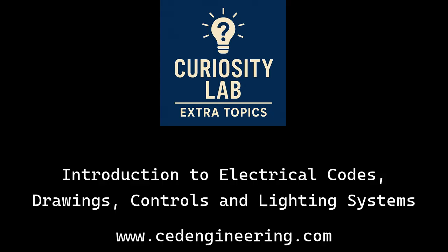Too dangerous. Wow. Okay, so beyond wearing the right gear, the physical space around electrical equipment matters too, doesn't it? What do the codes say about that? Yes, Article 110.26 is very clear. Access and working space shall be provided and maintained about all electrical equipment to permit ready and safe operation and maintenance. What that really means is you can't just stick electrical panels or switchgear in any old closet or tight corner.